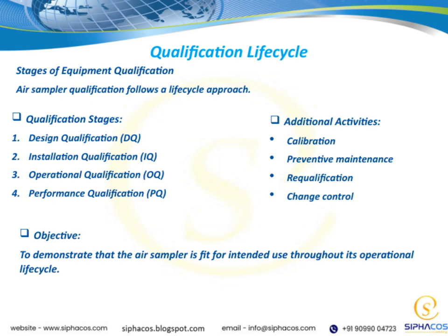Preventive maintenance involves routine checks and servicing to prevent unexpected failures. Requalification is performed periodically or after significant changes to confirm the sampler continues to meet specifications. And finally, change control helps us manage any modifications systematically, ensuring they don't compromise the device's performance.